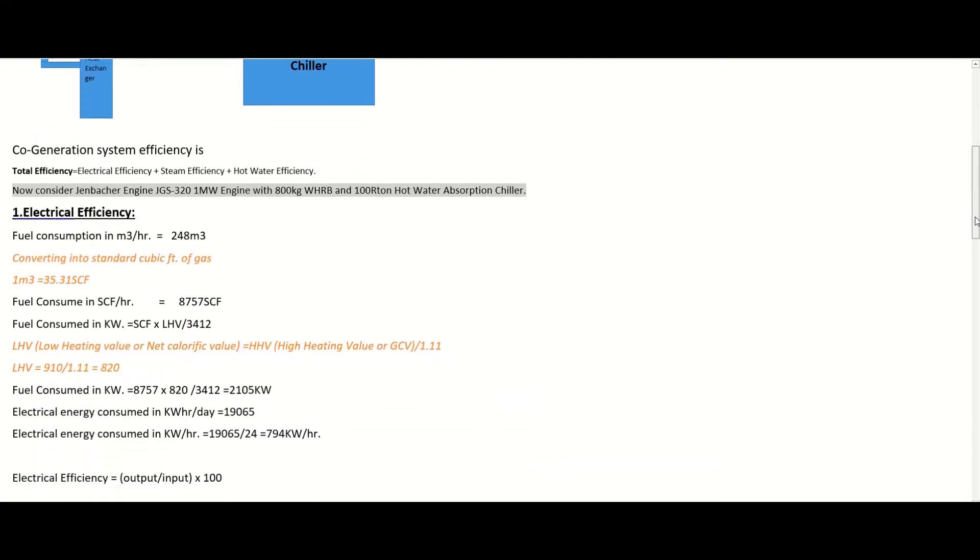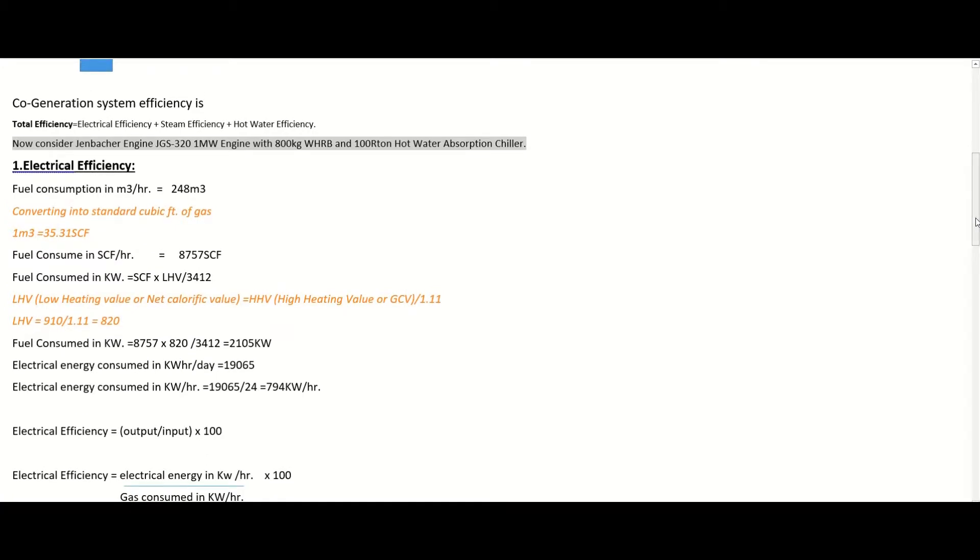The efficiency of this complete system is called the cogeneration system efficiency. Cogeneration system efficiency is basically equal to the electrical efficiency from the gas generator, plus the steam efficiency from the waste heat recovery boiler, plus the hot water efficiency from the hot water absorption chiller. A very important point to note is that for all systems — gas generator, waste heat recovery boiler, and hot water absorption chiller — the input is the same, which is natural gas fed into the gas generator.